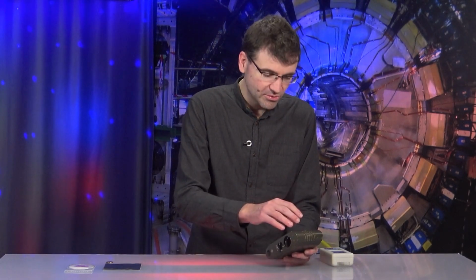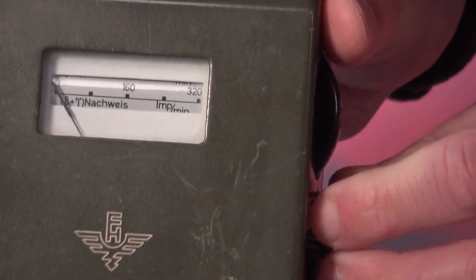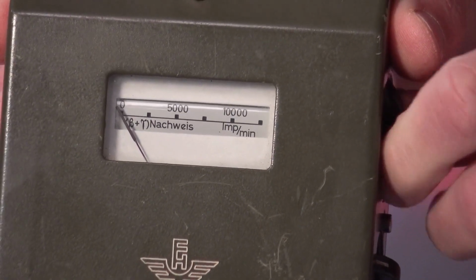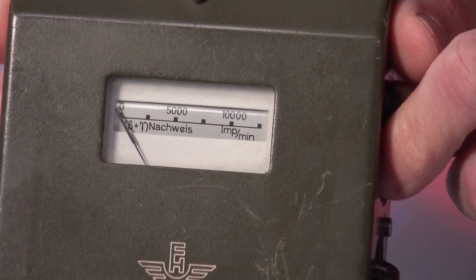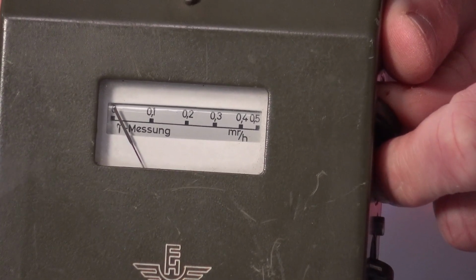But beta radiation cannot, or only to a very small extent. And so you can distinguish between these two types of rays. So, if we go back here, I can show you the same thing again in the display. So we can change to different scales, or here, you can see beta and gamma detection. And if I switch further, then we only see the gamma radiation here.